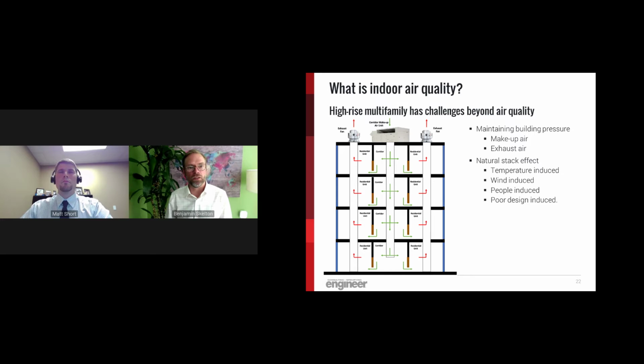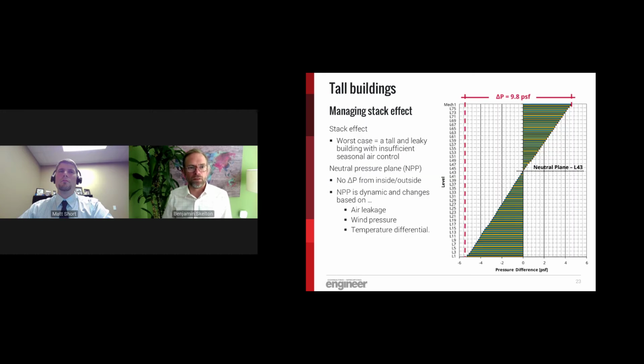Stack effect occurs in a building due to its height, based on temperatures, indoor to outdoor, wind speeds, and of course, people. And poor design is one thing I put on here. If you have things that directly expose lobbies to stairwells, elevators, things where there aren't pressure breaks or things to help manage the stack effect, that's going to impact your air quality. One of the things we deal with a lot in multifamily buildings is odor control, odor from other units infiltrating into other people's units because of things related to stack effect, building ventilation, and such. So generally, these buildings have a makeup air unit and exhaust systems, all with variable speed drives, and those modulate to try to control pressure at different areas and levels and manage this stack effect.